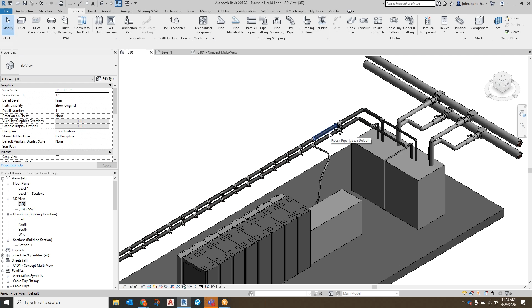Rich, if you've got something already put together, please share it and we'll take a look, because that's the kind of work we'd want to do. I know we're at the end here, but I'd also caution the team: we've got this divide between the infrastructure piping and the piping direct to the IT equipment, and there's rapidly evolving technology and thinking on how this is done. The group should be careful with material compatibility and fluids as to what we specify on the IT side of those piping loops.